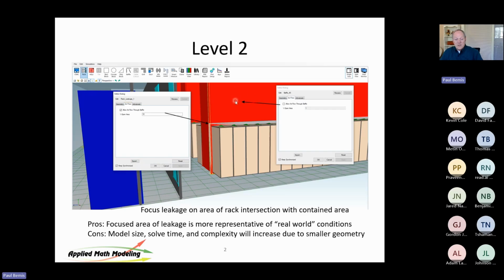And that's not leaking because they generally don't. They're made of solid material. The end caps are generally made of solid material. The leakage occurs here. It occurs around the perimeter of this rack. So you can set the rack up off the floor by a few inches. You see I've got it up off the floor 3 or 4 or 5 inches so that underneath that rack I can model the behavior of leakage.